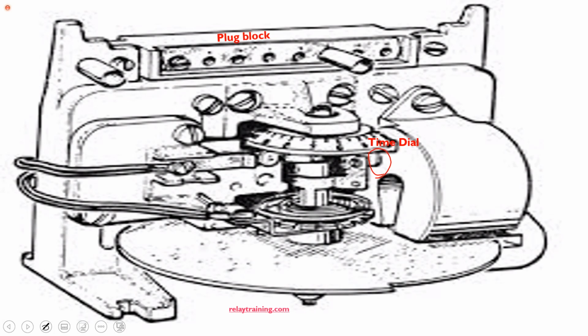So depending on the time dial that I'm using, if I were to turn it, the lower the number on the time dial, the closer the fixed contact would be to the movable contact. Because remember, as I said, the rest position is over here. Are we clear with that? So if I had it at 1, the fixed contact, which is that little area there, would be closer to the movable contact. So the lower the number on the time dial, the closer the fixed contact will be to the movable contact, or in other words, the faster the relay will operate. So the lower the time dial number, the faster the operation.